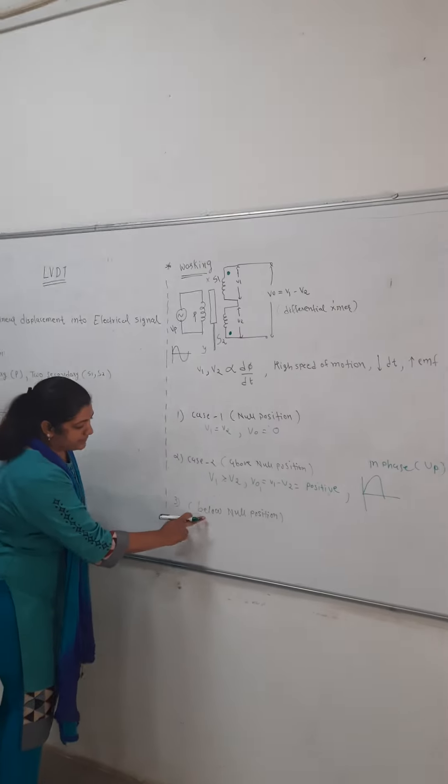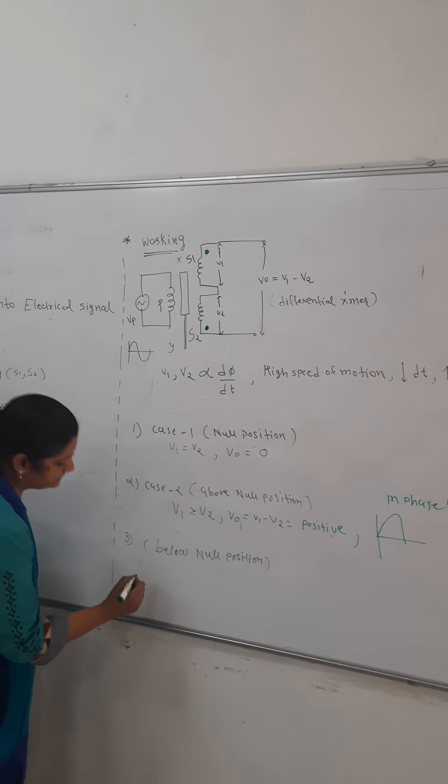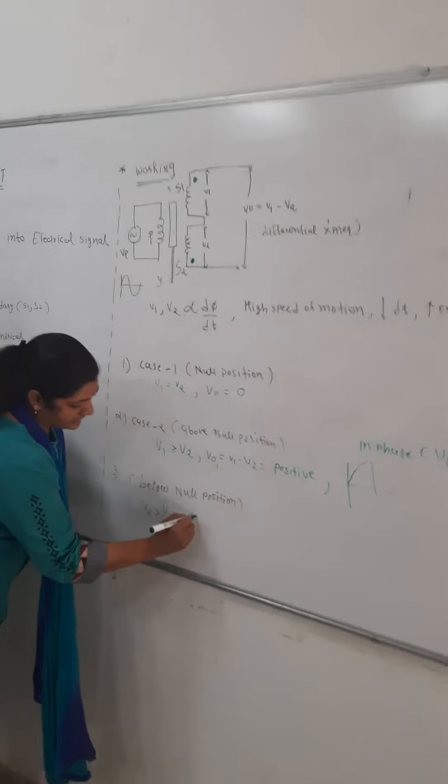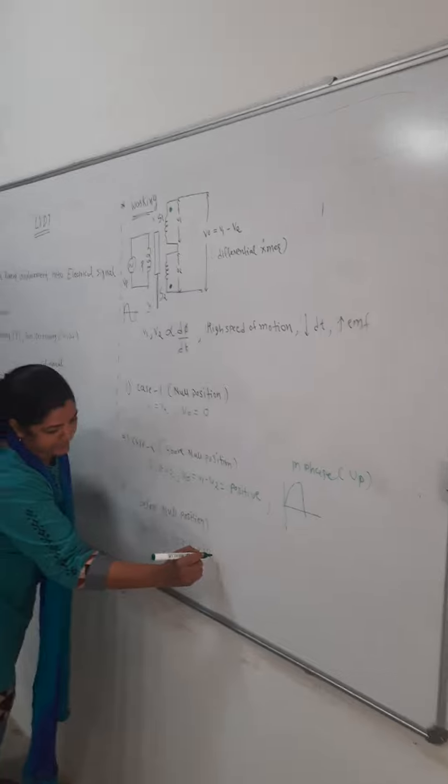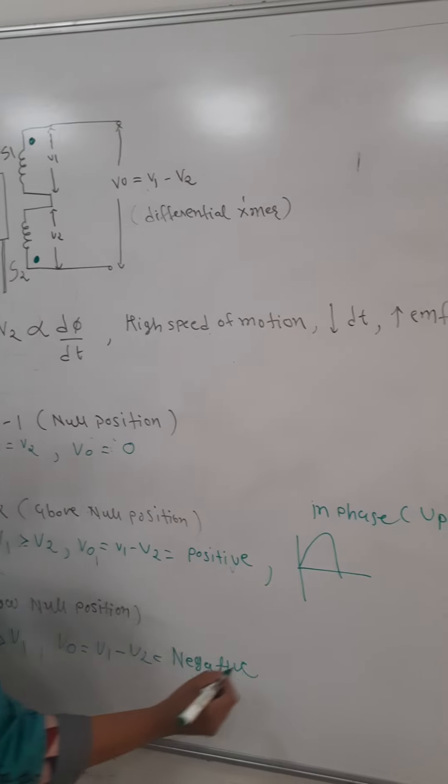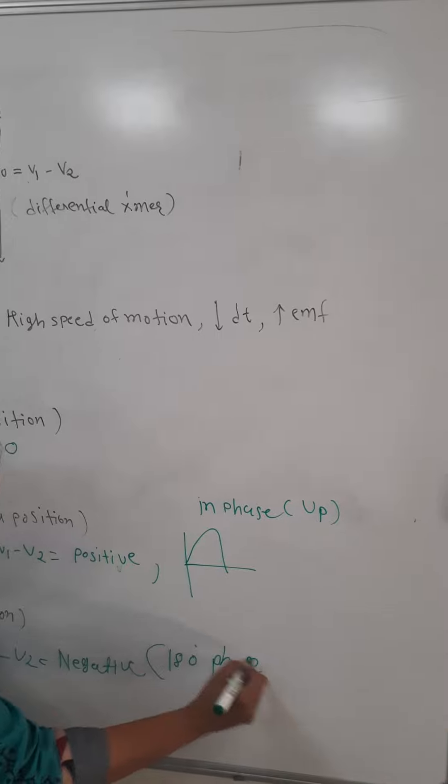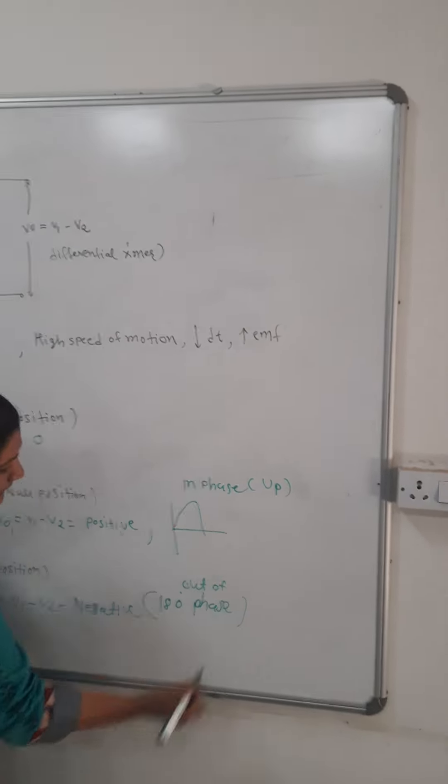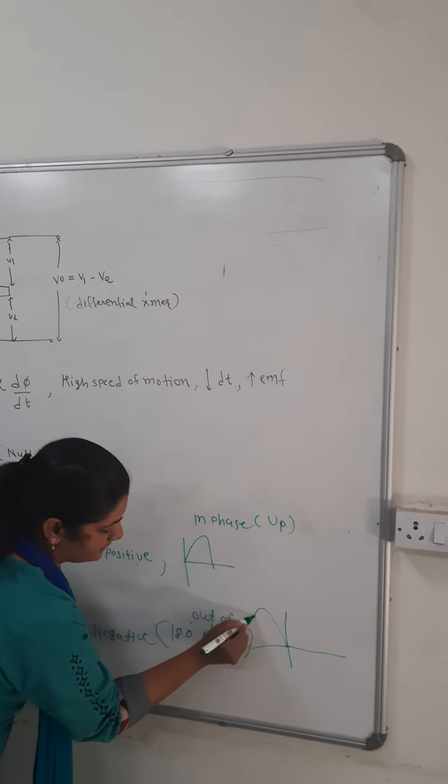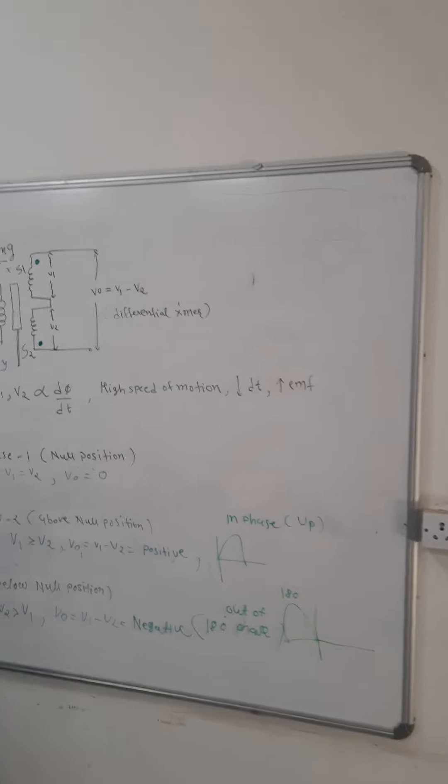Now, consider another case below null position. You can imagine that now the core is downside of the null. Same like the previous one. Now, V2 will be greater than V1. And V0 as per the formula V1 minus V2, we have a negative reading. Negative in the sense we can say that the output voltage will be 180 degrees out of phase. Or in phasor, we can say if this is our primary side, at 180 degrees, we have the V0 for case number 3.